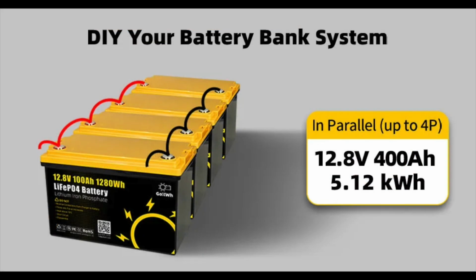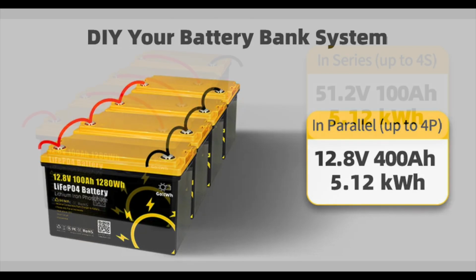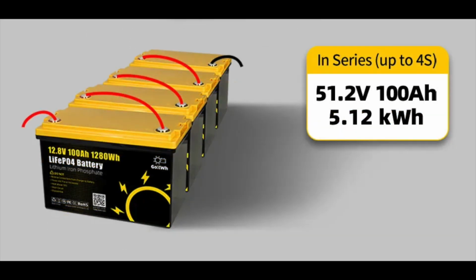Okay, these batteries can be connected in up to 4 batteries in parallel, which gives you 400 amp hours at 5.12 kilowatt hours. It can also be connected up to 4 in series, which provides 51.2 volts at 100 amp hours or 5.12 kilowatt hours.